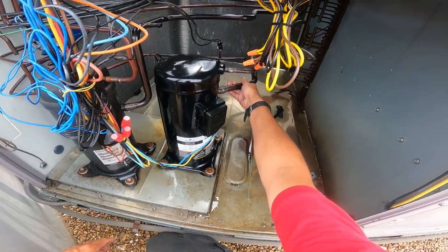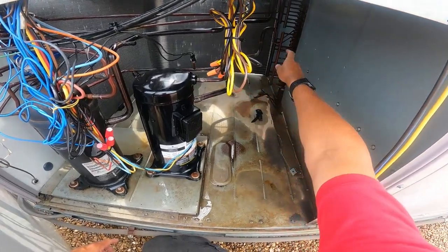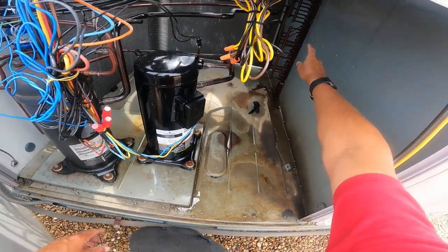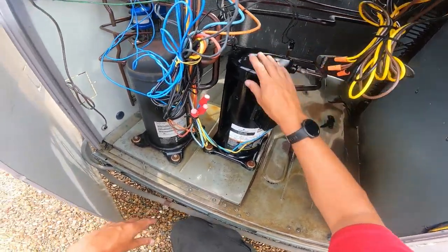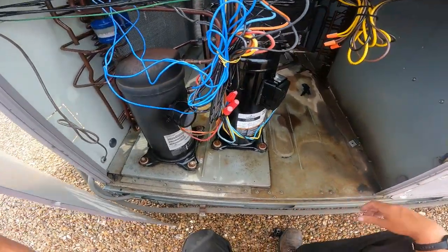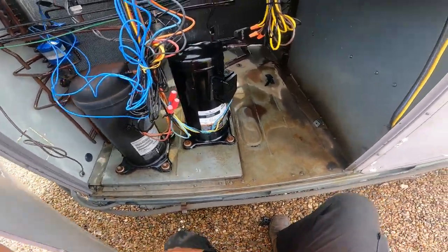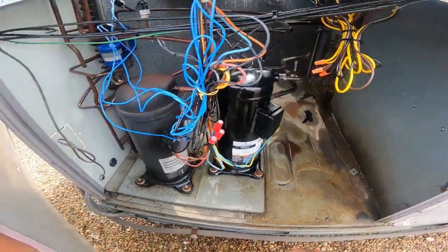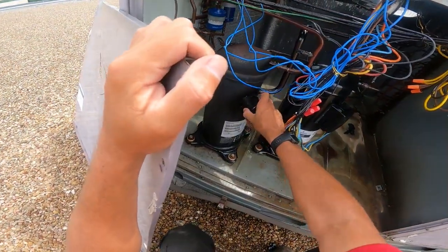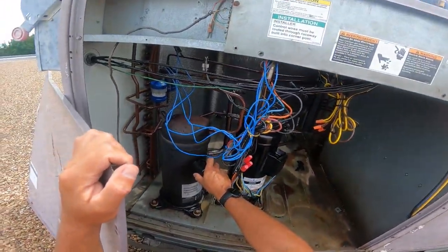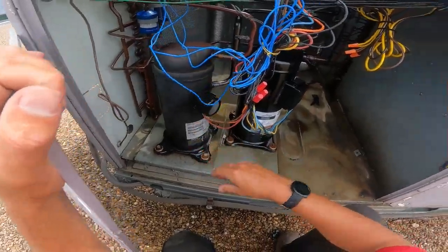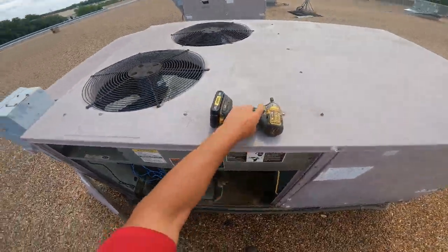So we need to get this side running, which look, it has been running. We've got condensation on the bottom of the evaporator coil, which is where stage 2 runs. So it's been going, and I like to see the condensation. We're going to leave stage 2 running. Stage 1, I'm going to disconnect here. Actually, no, because it's not a harness. I'm going to disconnect it from the contactor.